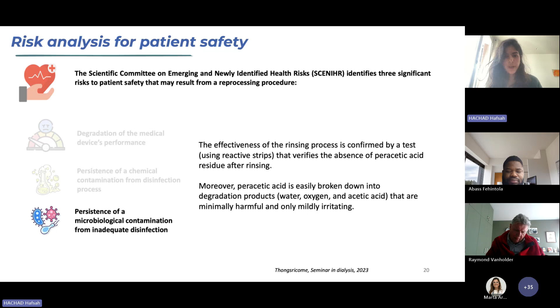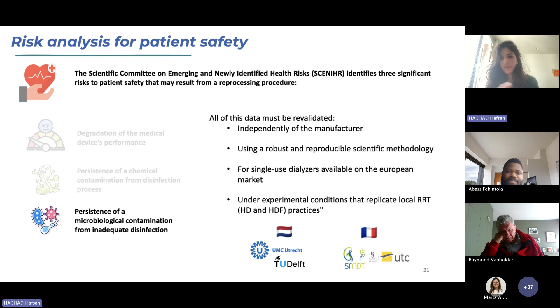And so all this data must be revalidated independently of the manufacturer using a robust and reproducible scientific methodology, and also transposed to the European context, because we have only single-use dialyzers available here, and all the tests that have been done with the ClearFlux were done on dialyzers that were labeled reusable by the manufacturer. And we have to test this under experimental conditions that replicate local dialysis practices in Europe, including HDF. And this is work that will be done in the next month in Utrecht, in the Netherlands, and also here in France.